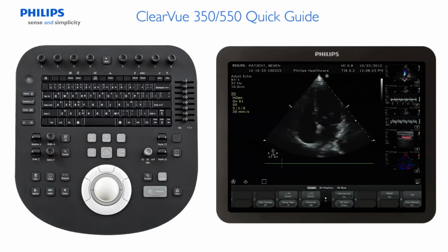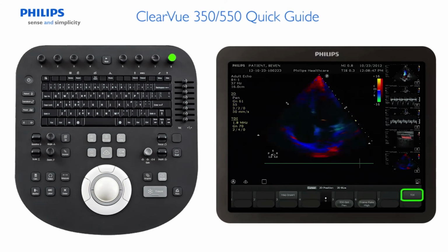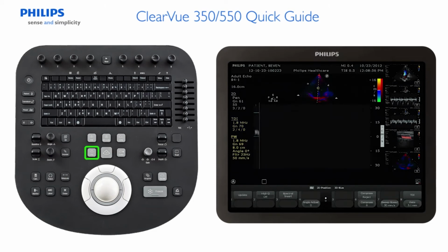The following section will describe tissue Doppler imaging, which displays the axial velocity of myocardial tissue and can be used in combination with pulsed wave Doppler or M-mode imaging. Tissue Doppler imaging is available only with sector transducers and cardiac presets. Press the quick key to activate tissue Doppler imaging in 2D mode. To activate pulsed wave Doppler, press PW while in tissue Doppler imaging. To perform tissue Doppler imaging calculations, follow the same procedure as pulsed wave Doppler measurements.